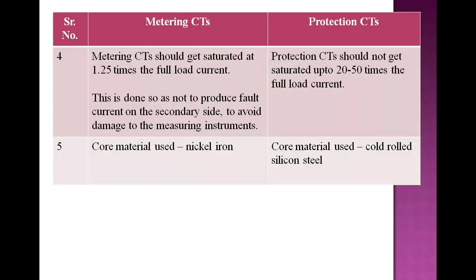Metering CTs should get saturated at 1.25 times the full load current. This is done so as not to produce fault current on the secondary side, to avoid damage to the measuring instruments. Protection CTs should not get saturated up to 20 to 50 times the full load current. Core material used for metering CTs is nickel iron, while core material used for protection CTs is cold rolled silicon steel.